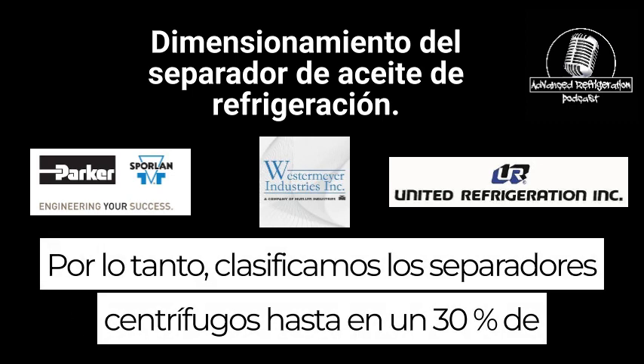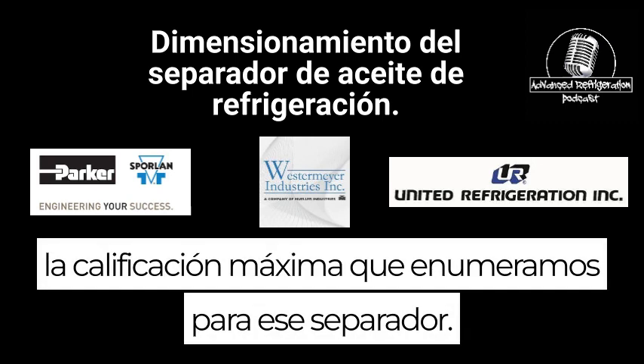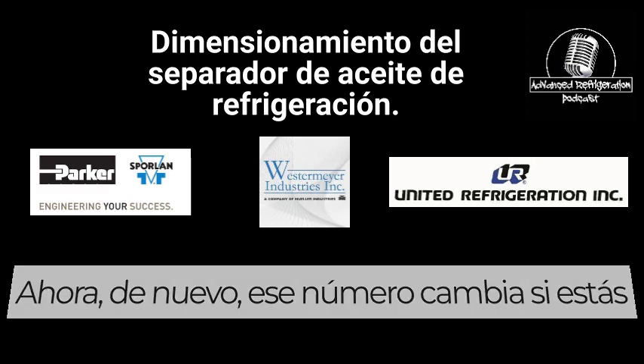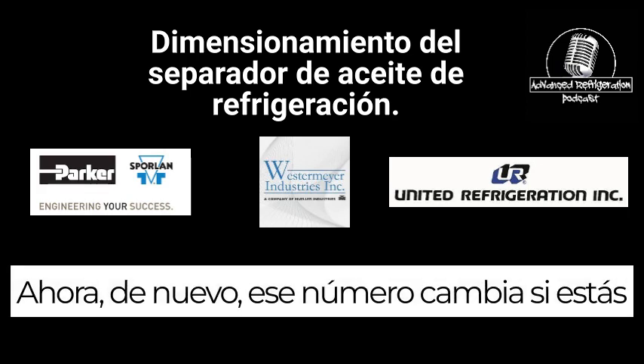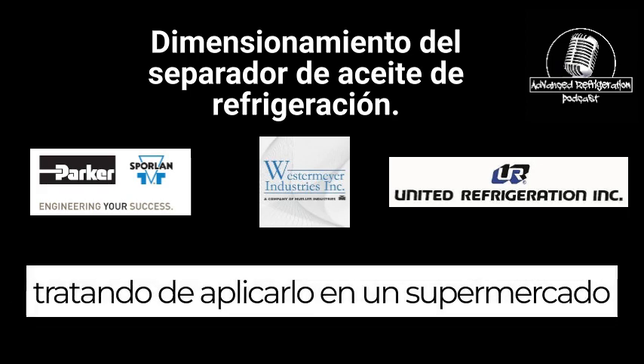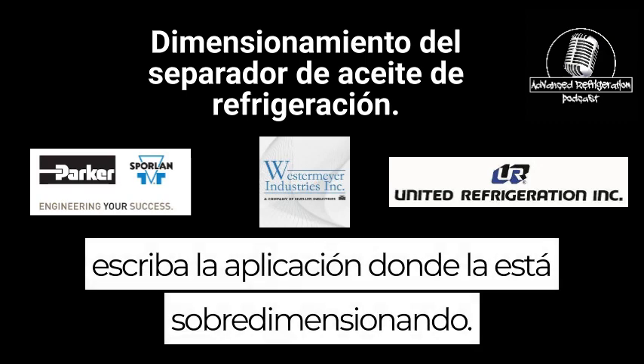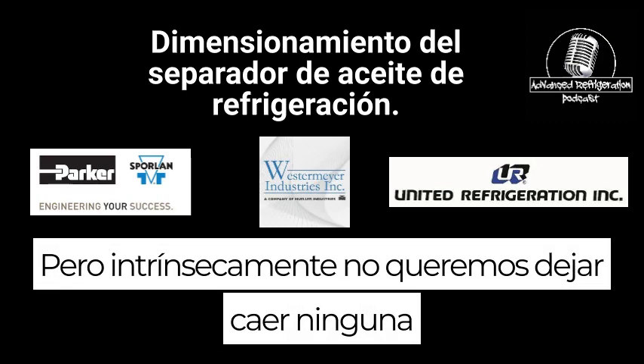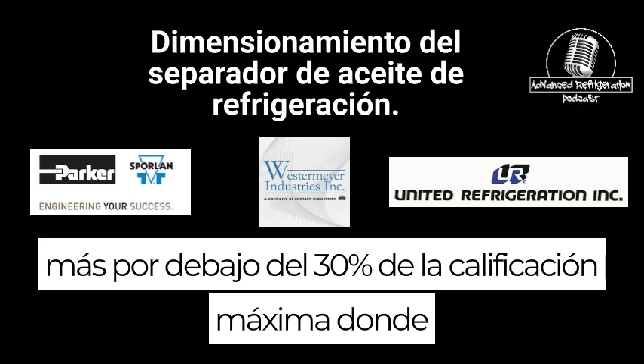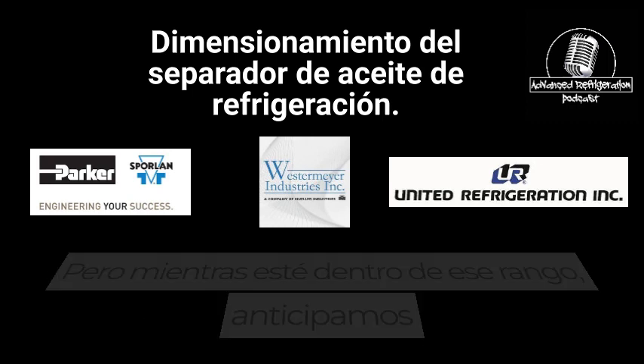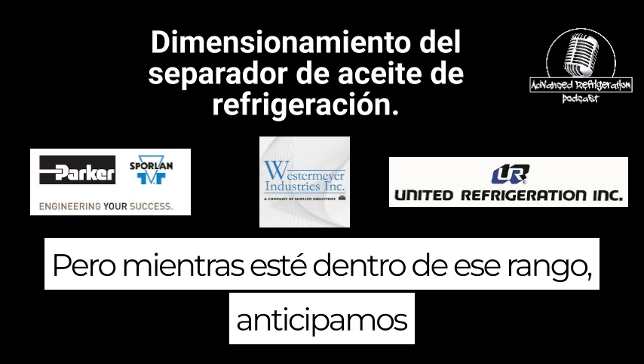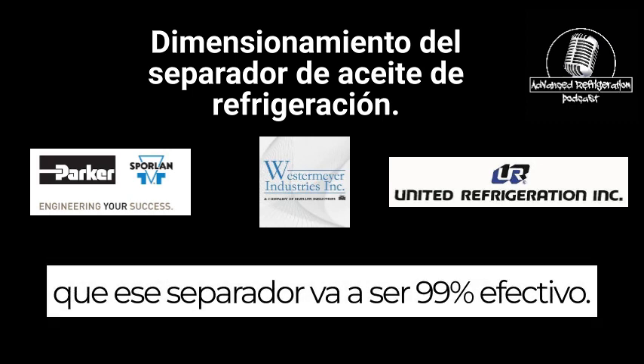So we rate the centrifugal separators down to 30% of the maximum rating that we list for that separator. Now, that number shifts if you're trying to apply it in a supermarket type application where you're oversizing it. But inherently, we don't want to drop any further below 30% of the max rating, or your efficiencies are going to drop. But as long as it's within that range, we anticipate that separator is going to be 99% effective.